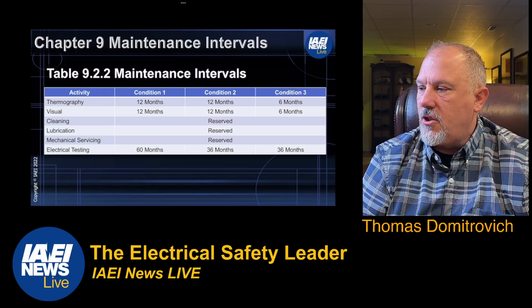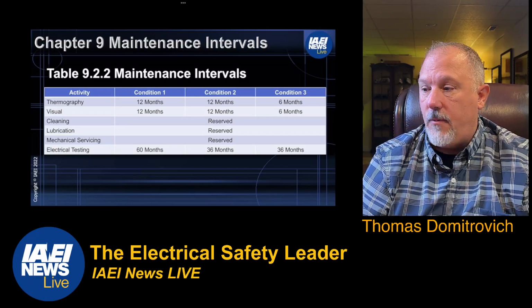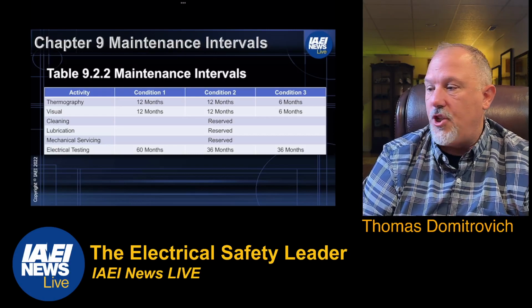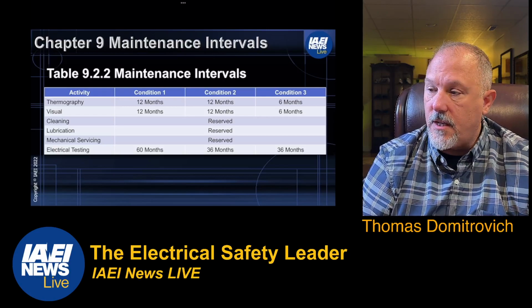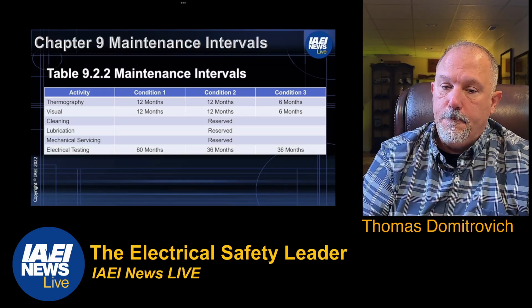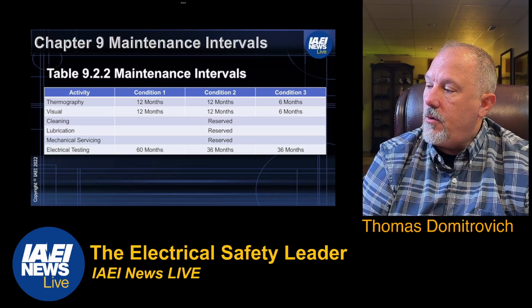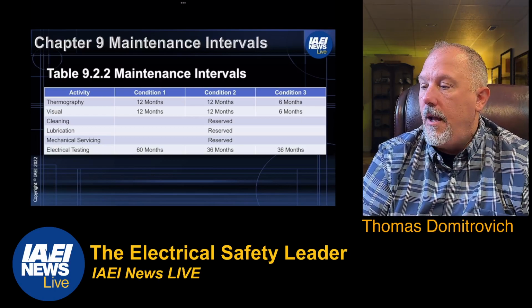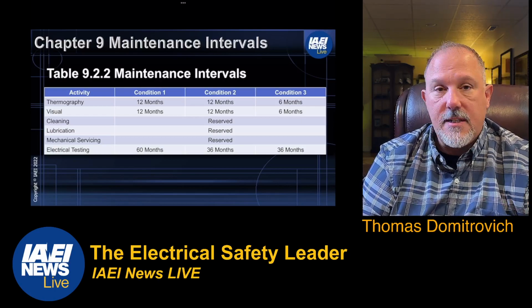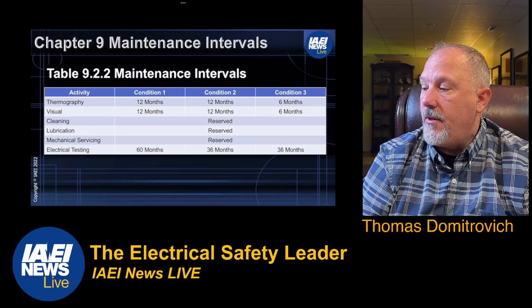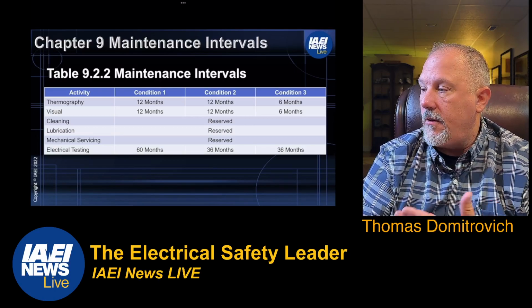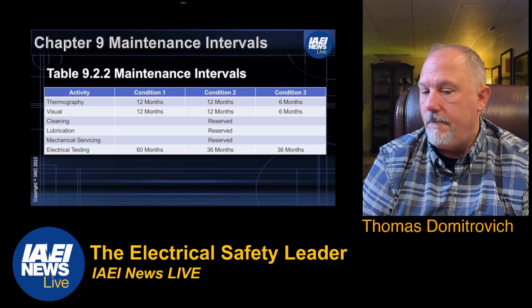We have visual inspections—remember, we had visual and electrical testing, but no cleaning, lubrication, or mechanical servicing listed. So visual is 12, 12, and 6. Electrical testing is every 60 months—that's 5 years—then 36 months, 3 years, for condition 2, and 36 months for condition 3.